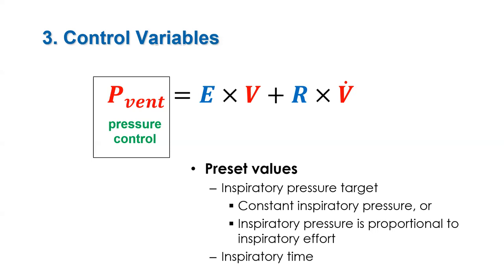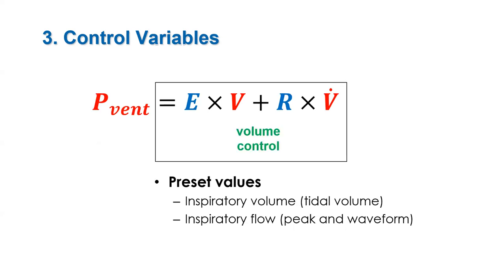As the operator, you either set the inspiratory target pressure or the constant of proportionality between PVent and PMUS in modes like NAVA and PAV. On the other hand, volume control means that the ventilator controls the right-hand side of the equation. This means that both tidal volume and peak inspiratory flow are preset. Therefore, changes in elastance and resistance cause changes in the pressure waveform only.